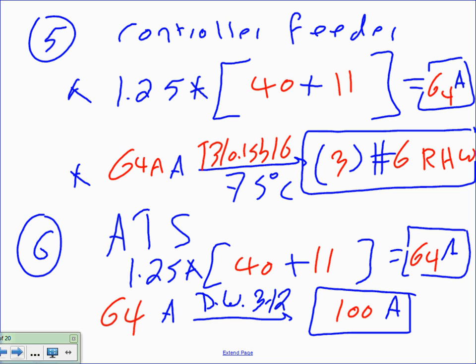We use disconnects for them, absolutely. For the sake of the calculation, we use the disconnect sizes as the ATS sizes. Now, it might not be exactly the same, but in real life, typically they're not far off. You're going to go to a manufacturer, find the standard that they use, and pick the next standard. Make it easy for you here, standardize it a little bit. 100 amp is a standard. Any question? Dustin, my friend, does it make sense? No? Yes? Okay, so that's basically the ATS that we're going to use.